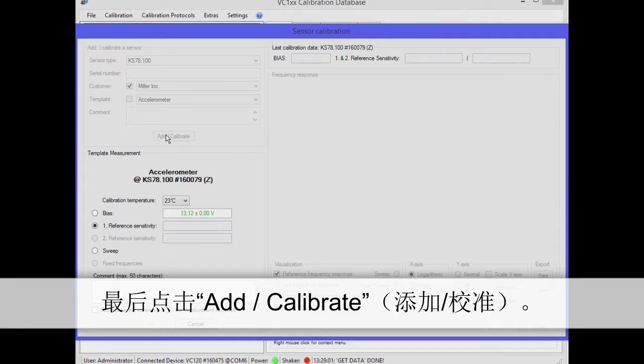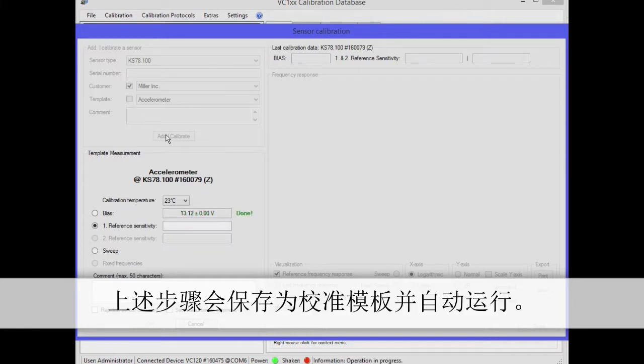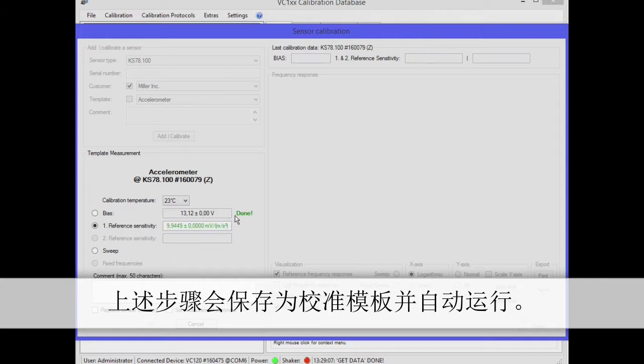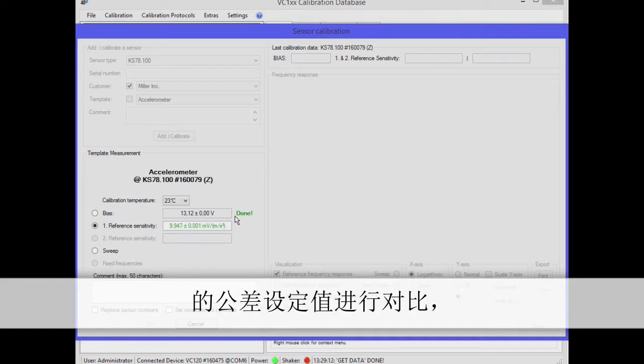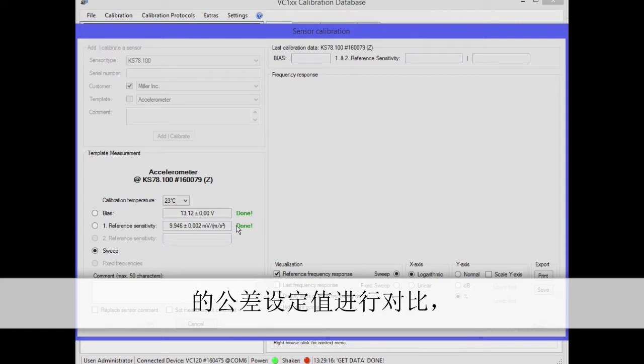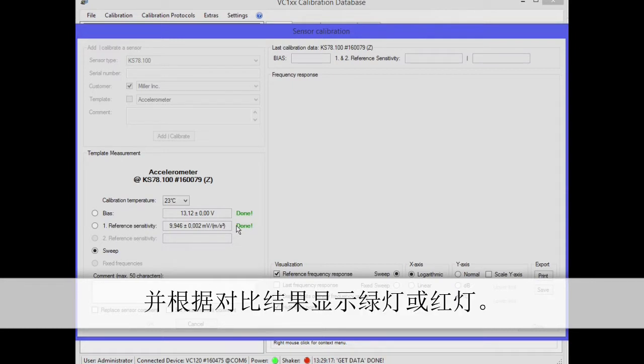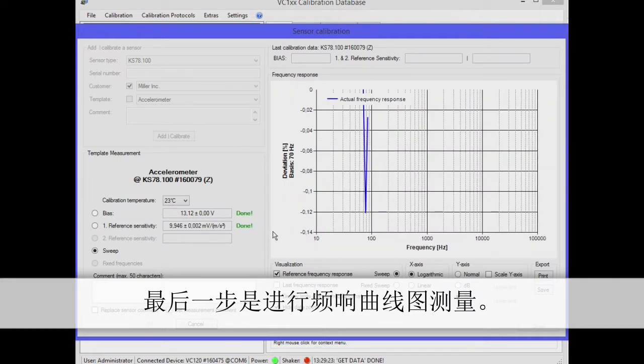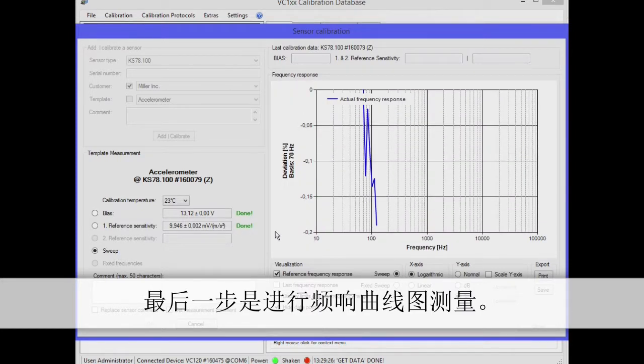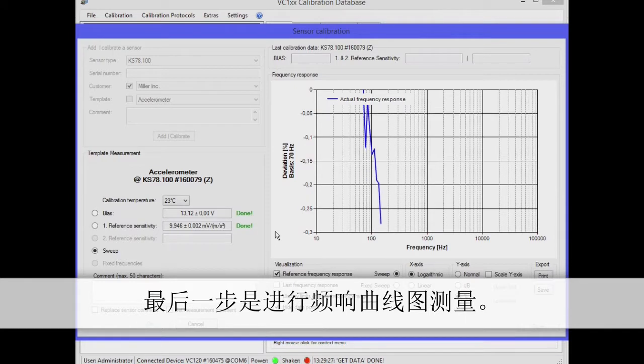The measured values are compared with the permissible error margins from sensor types and depending on the permissibility, they appear in green or red. As the last step, the frequency response graph is measured.